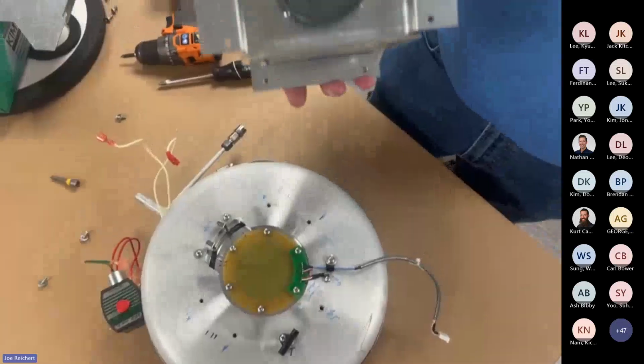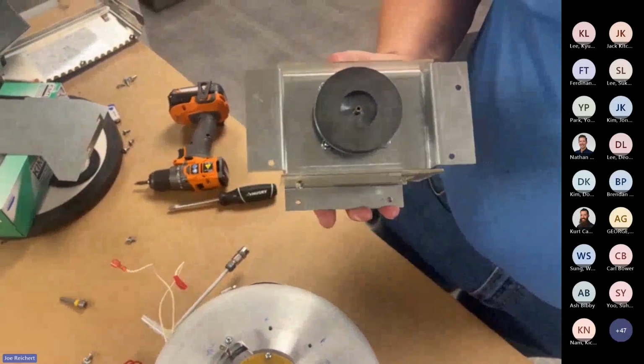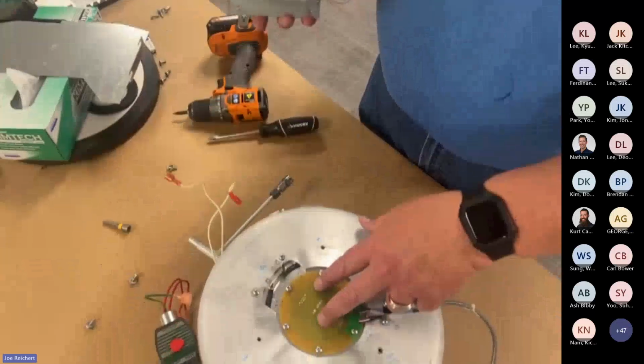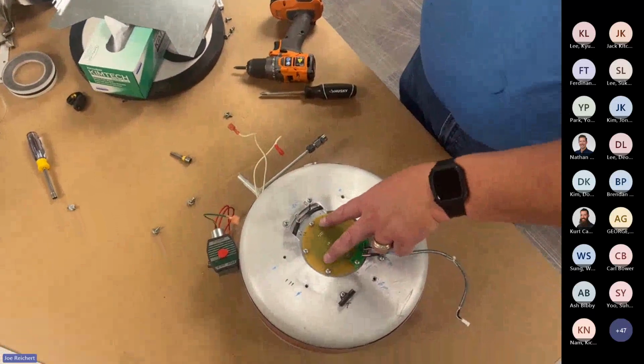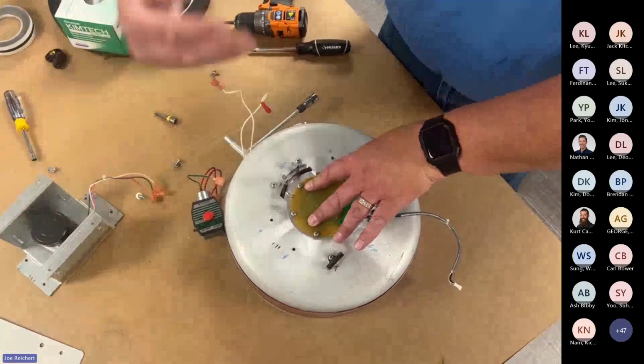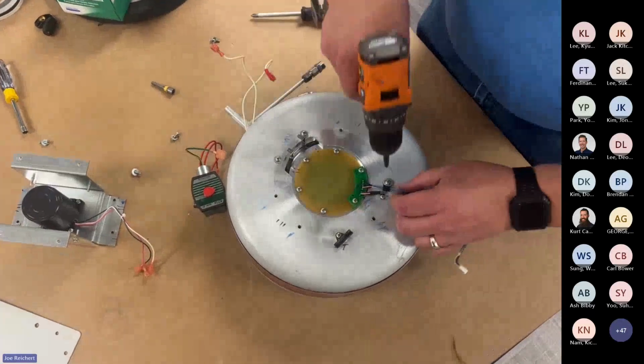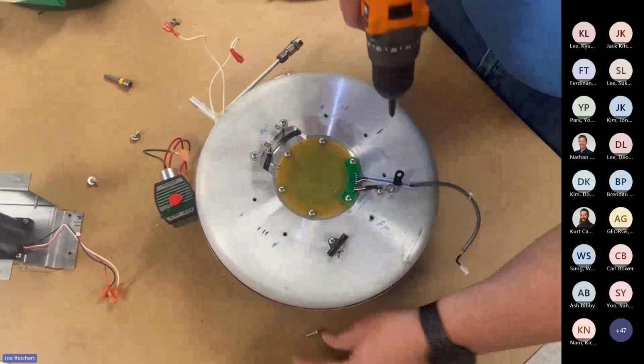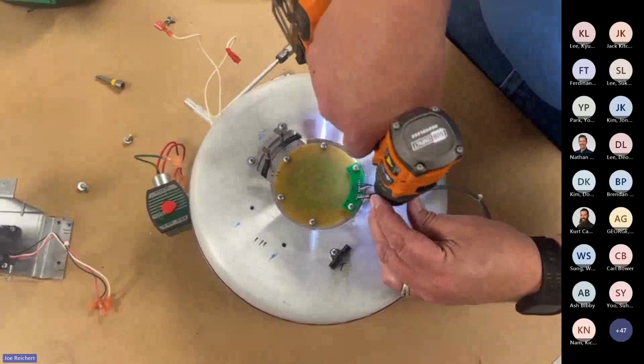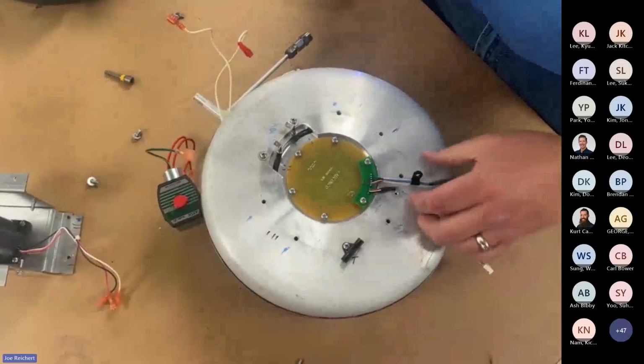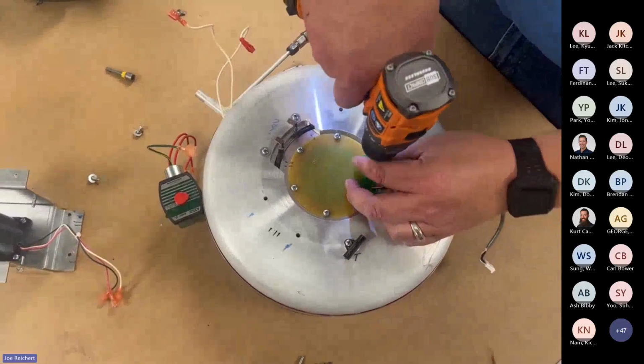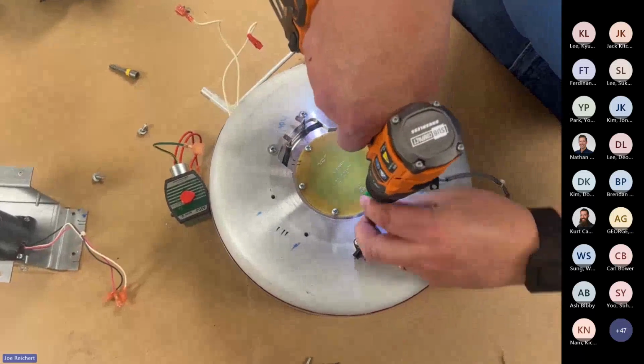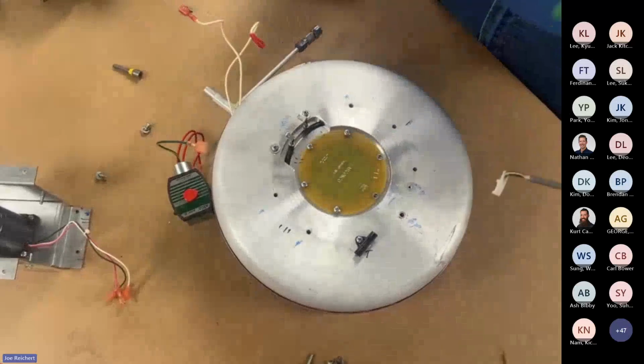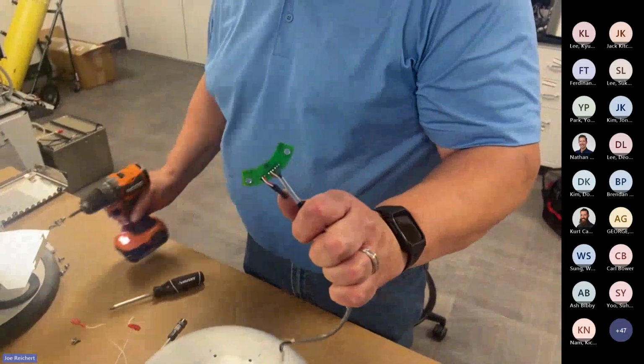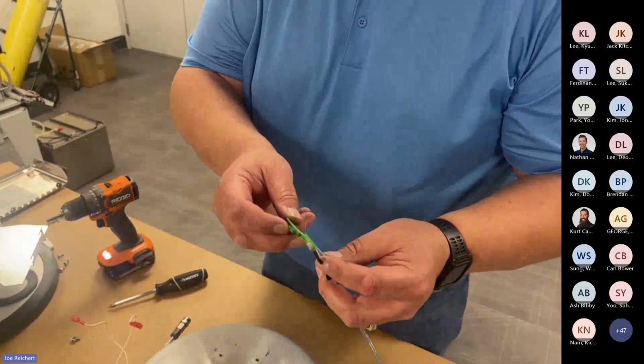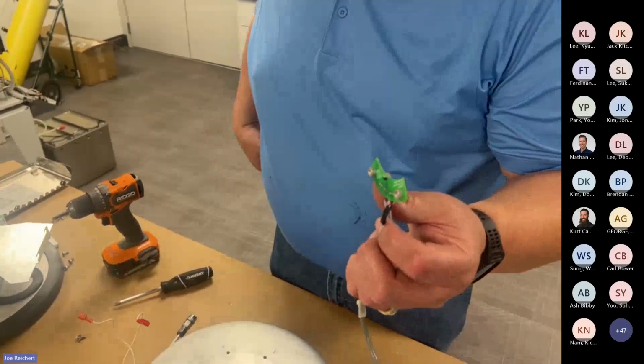Here you see the magnet that drives the shaft. The shaft does not have a direct connection to the motor, it uses magnets. The magnet here goes through the seal plate on top of the chamber, and it interfaces with another magnet on the other side that's attached to the bottom of the rotor or the shaft. And to get to those, we can see it. The temperature probe and the Hall effect sensor are together. This is in one piece. The little black part is your temperature probe, and this is the piece that detects the rotation, the RPMs of your rotor that's spinning.